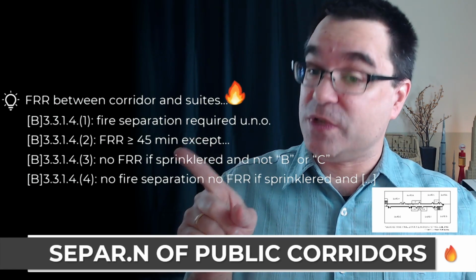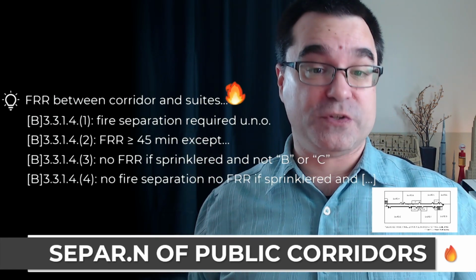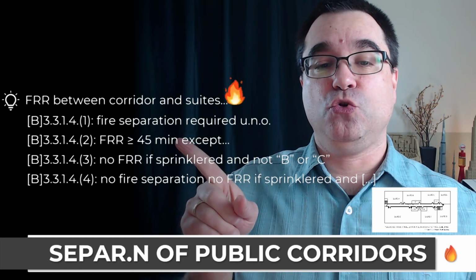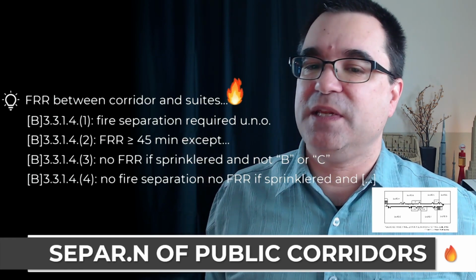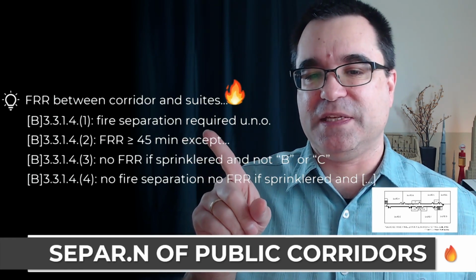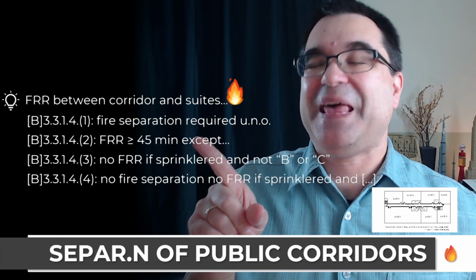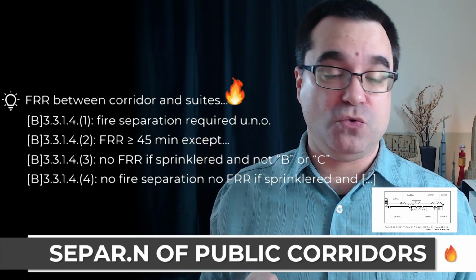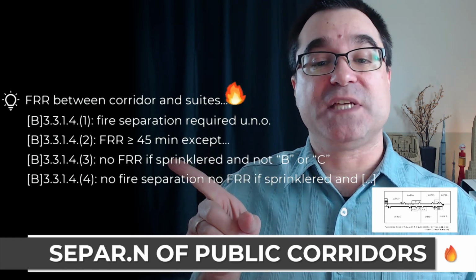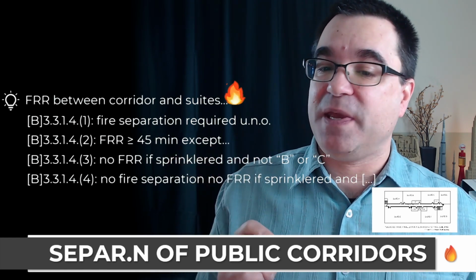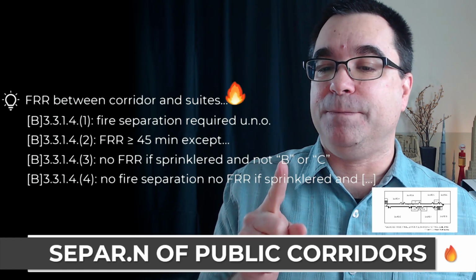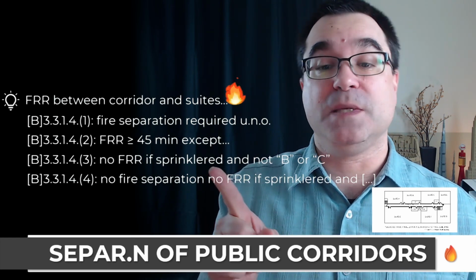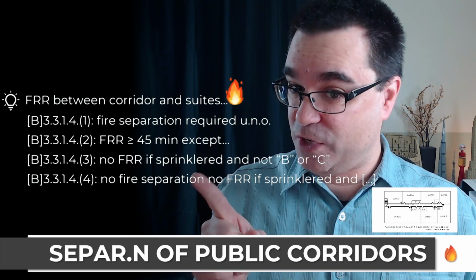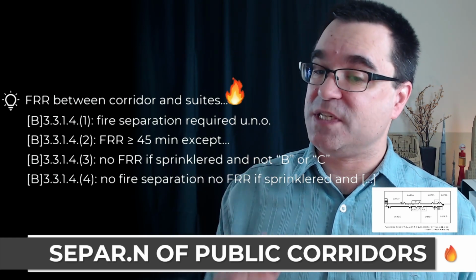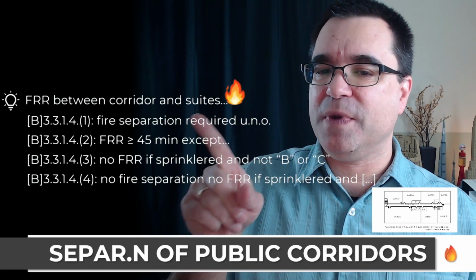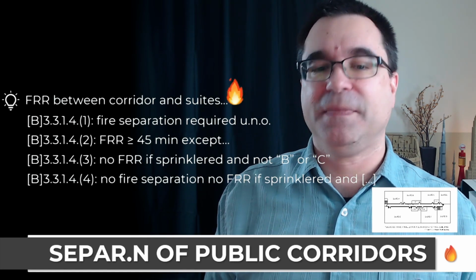When it comes to fire resistance ratings for those fire separations, sentence 2 says that the fire resistance rating needs to be more than 45 minutes, except for those exceptions that you have under sentence 2. Now, under sentence 3, if that space is not a B or a C major occupancy, but is sprinklered, then no fire resistance rating is required, but it still must be a fire separation.